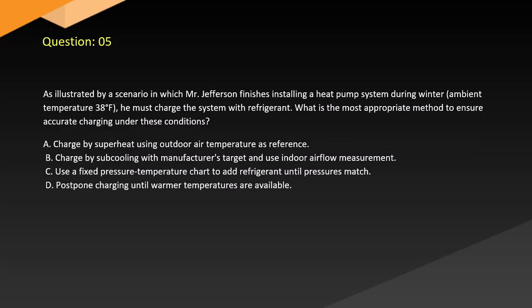Question 5. As illustrated by a scenario in which Mr. Jefferson finishes installing a heat pump system during winter, ambient temperature 38 degrees, he must charge the system with refrigerant. What is the most appropriate method to ensure accurate charging under these conditions? A. Charge by superheat using outdoor air temperature as reference. B. Charge by subcooling with manufacturer's target and use indoor airflow measurement. C. Use fixed pressure temperature chart to add refrigerant until pressures match.